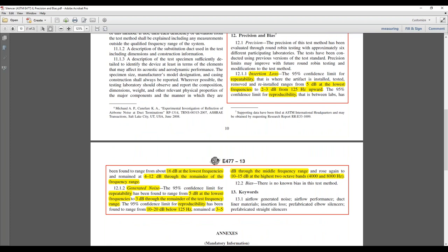right? So because when you do silencer testing, if you think about it, the size of the room to measure the correct wavelengths, the instrumentation itself is different, it's going to be impossible for you to get the same performance for the same silencer if you test it in the Price lab versus a vibroacoustics lab. So there's going to be a little bit of variance, and that's what you have to be understanding, if possible, on why silencers differ in performance a bunch. All right.